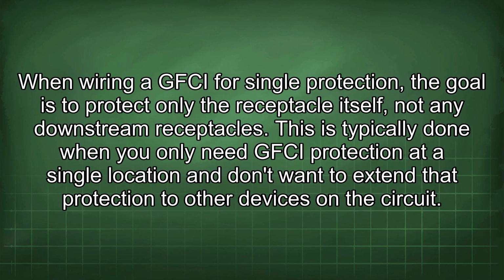When wiring a GFCI for single protection, the goal is to protect only the receptacle itself, not any downstream receptacles. This is typically done when you only need GFCI protection at a single location and don't want to extend that protection to other devices in the circuit.